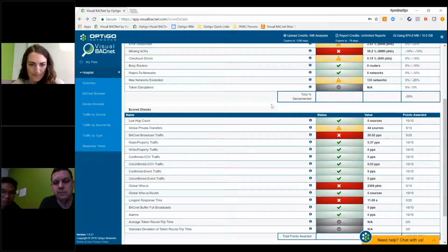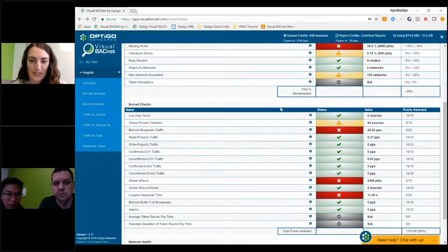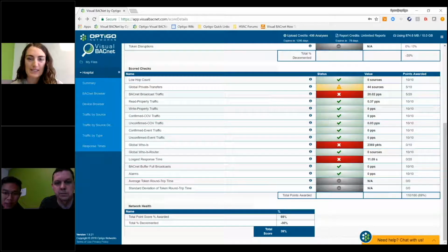Check out the global who-is. 2,369 global who-is in, what did we say, 2 hours? 2.5 hours. So this is a bit interesting, but down here is a score check. They're not as critical, they're more warnings to you, right? Let's start at the top before we get to the global who-is. We get all excited. There's a few global private transfers. That's just a non-BACnet way of sending some data up. So every vendor is going to have their own proprietary way.